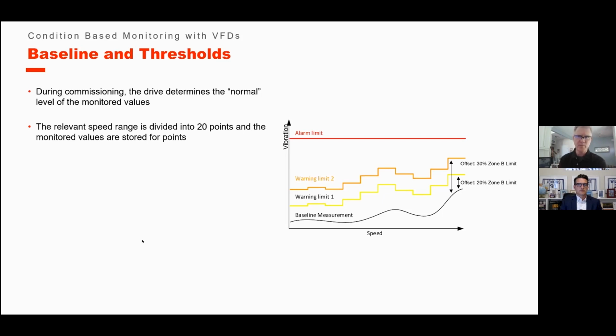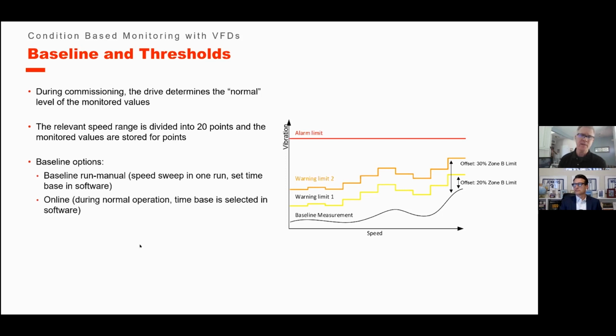And we store those data points for information on how the machine is acting, both motor stator-wise, with the integrity of the actual winding inside the motor, the load envelope on how the machine is handling, and the vibration envelope, how that machine is vibrating through the speed ranges. Because as speed changes, you also get different frequencies of vibration. So you have to have a good monitor of that. You have a couple of baseline options. You actually have a manual type of run baseline, and you'll see this when I do the demo on it. It'll make a lot more sense when you actually see it.